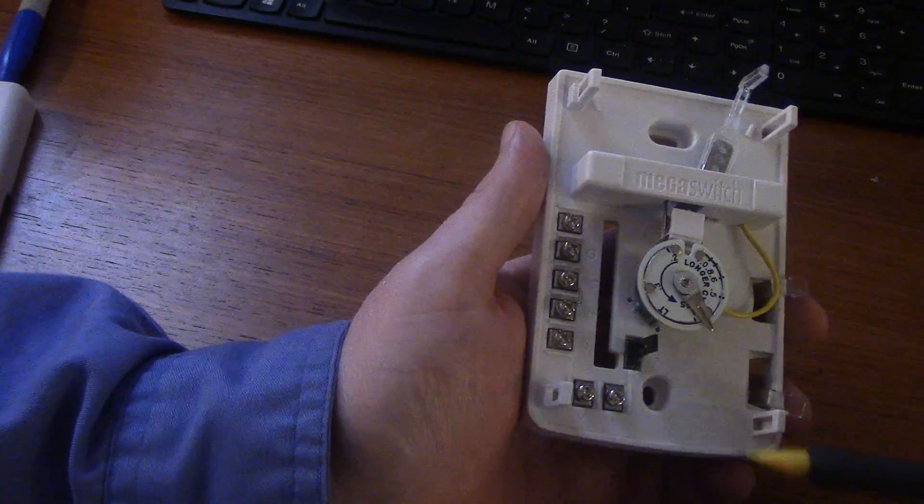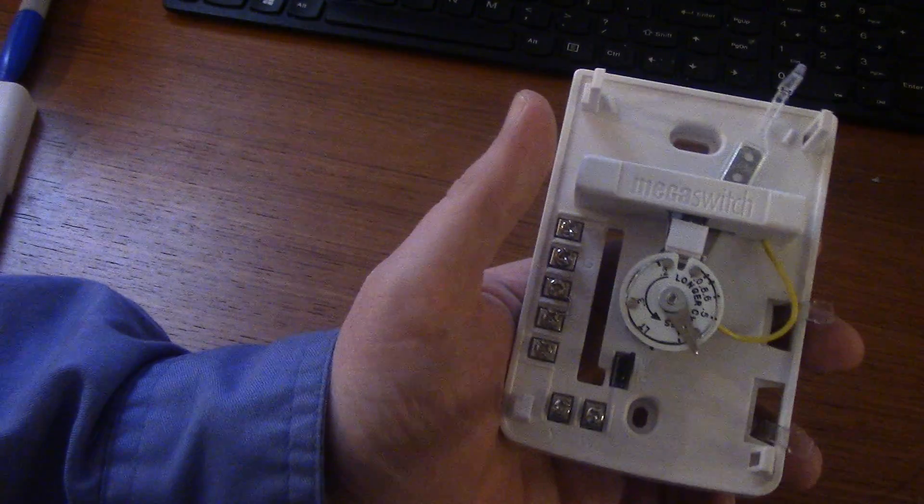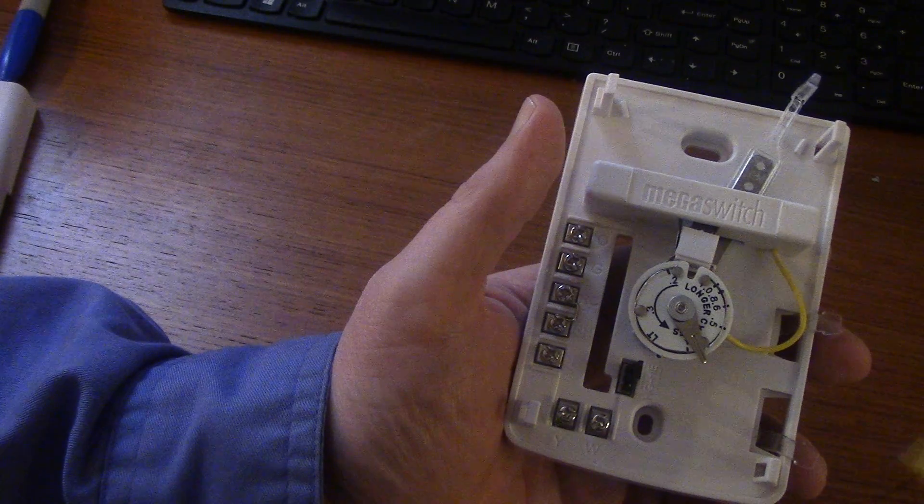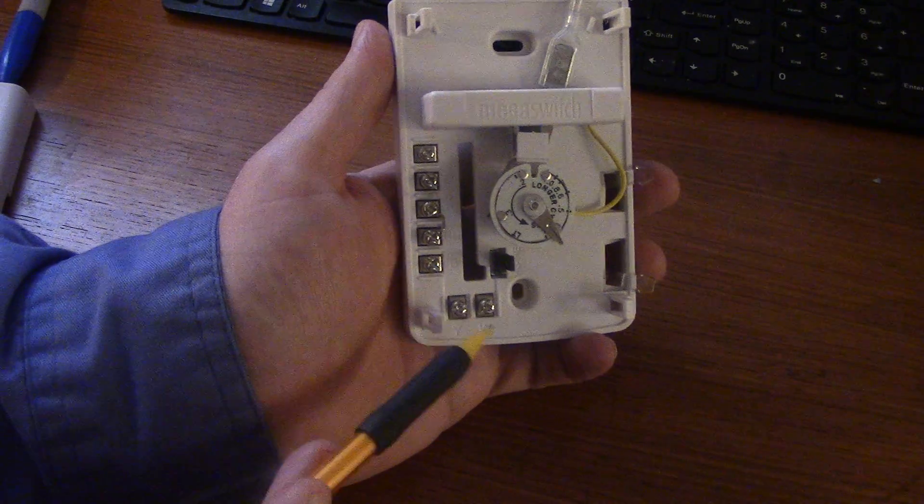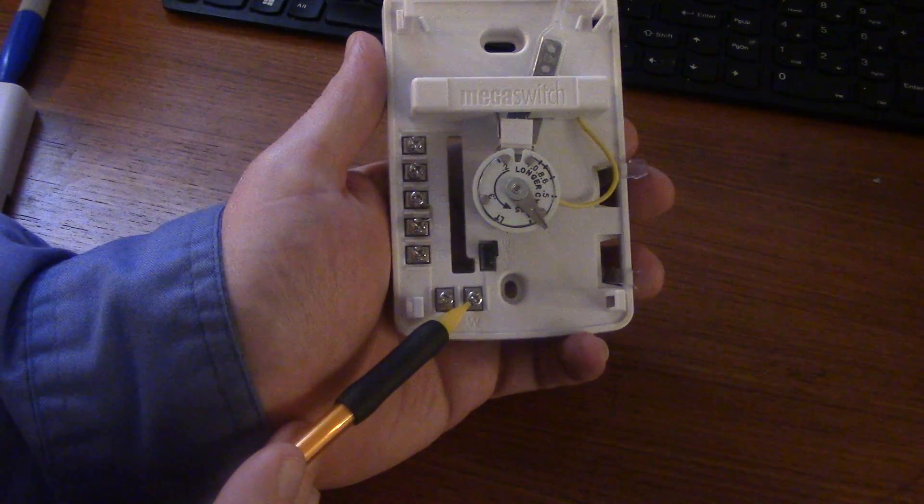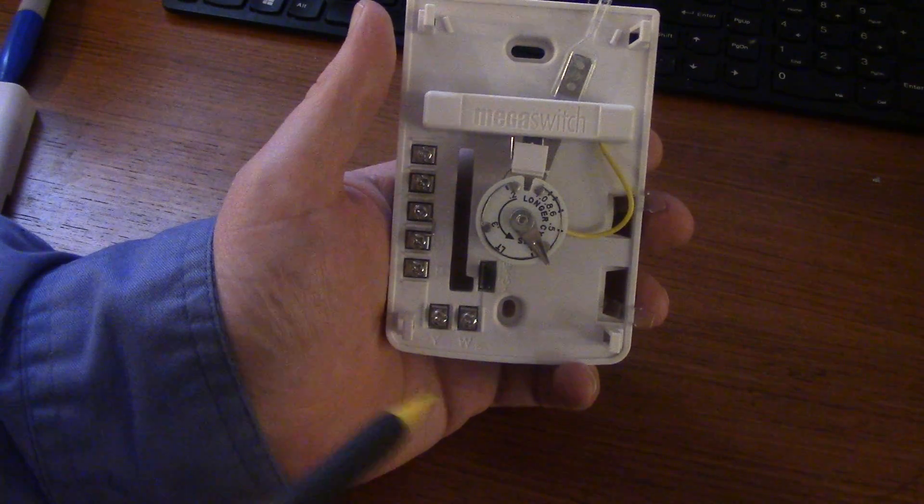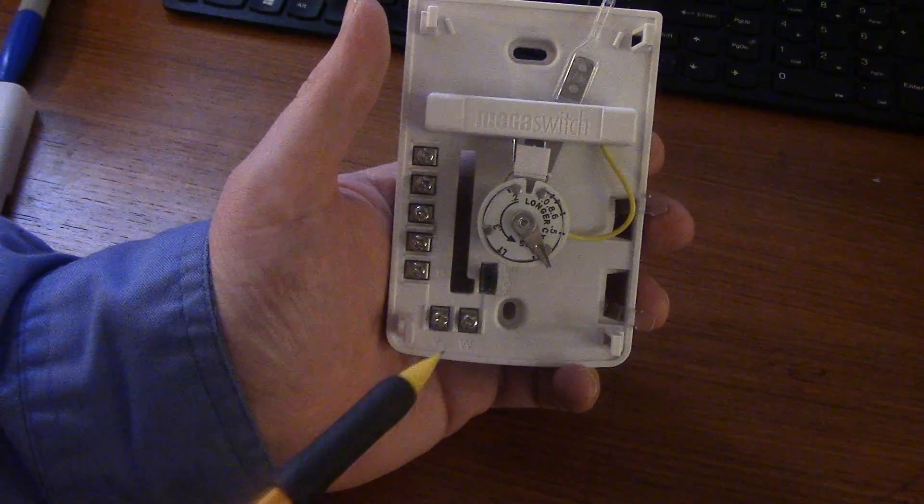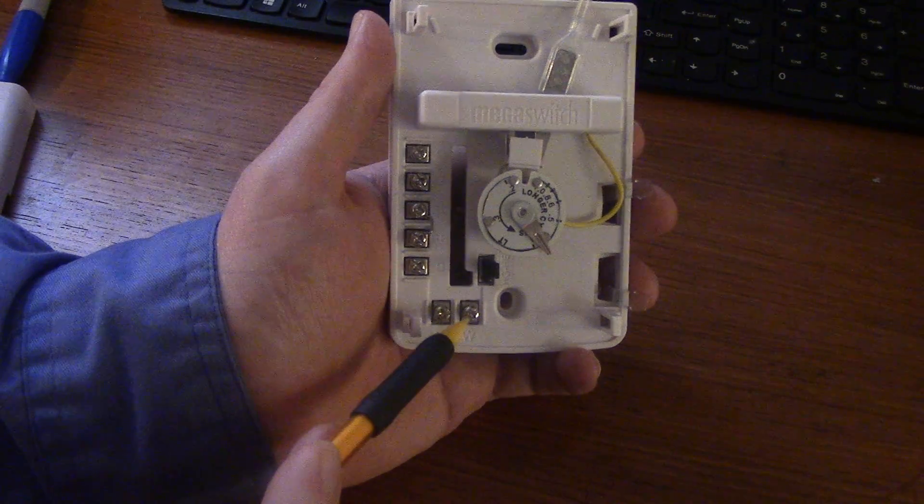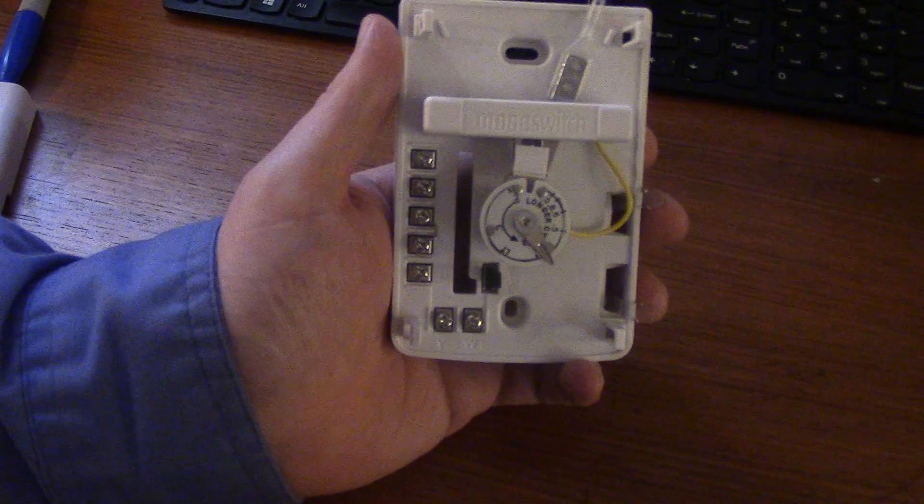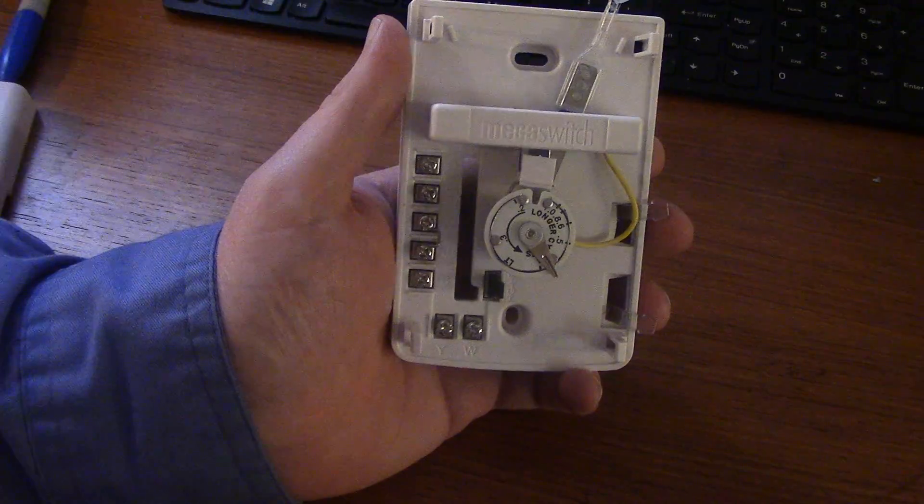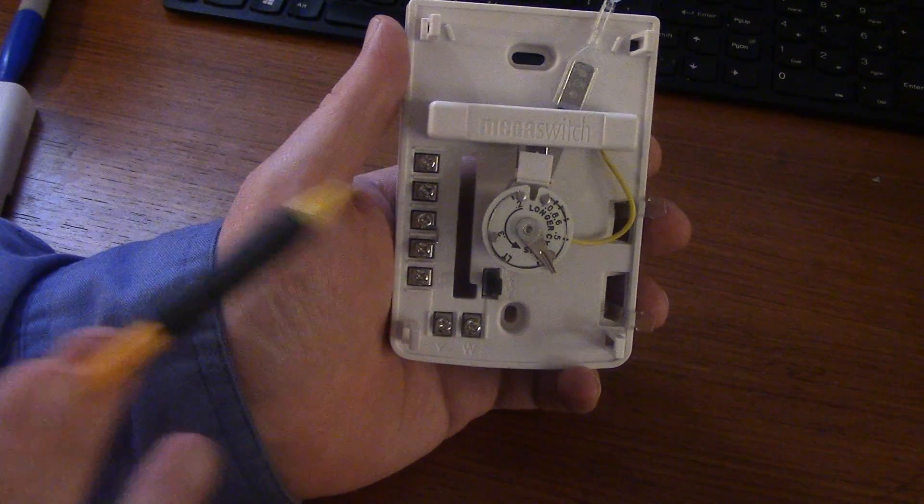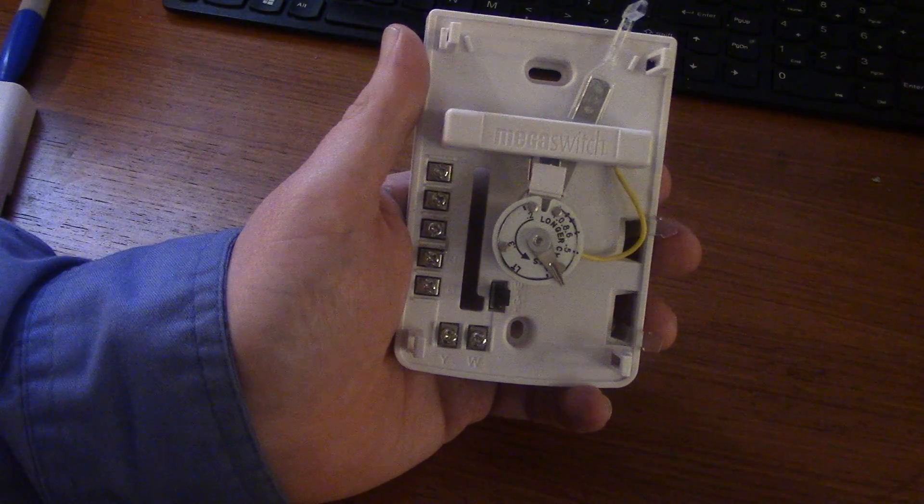Let's see - the heat anticipator. If you want to set it, you have to do what's called a 10 wrap. You'll essentially take - I do it at the thermostat - take the W wire off of here, hook like a jumper wire to it, put it around the clamp on your meter called a 10 wrap. So you wrap it around the amp clamp 10 times, then put the other clamp right back onto there. Run the furnace, wait for the blower to kick on, wait for everything to get going and you'll get an amp draw.